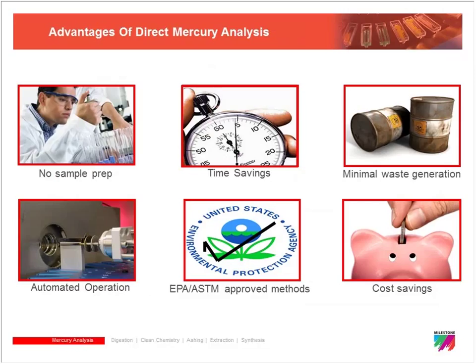So where a direct mercury analysis differs is, first, there's no sample preparation in terms of a digestion. So your sample can be placed directly into the system and analyzed. So you save a lot of time on the sample preparation step. So there's going to be no acid digestion, so you're not generating a large amount of acid waste, and you're also not having to purchase a lot of those acids used in the digestion process. The system itself works on a very automated basis due in part to the software, so that allows you to load up your samples into an auto-sampler tray and hit the start button, and away you go onto your analysis.